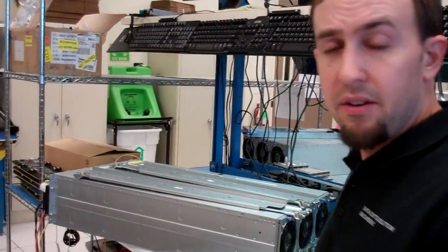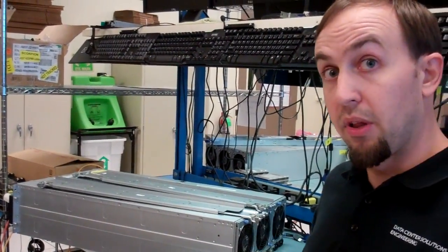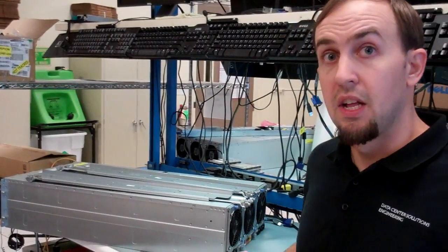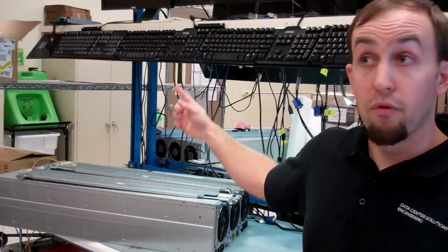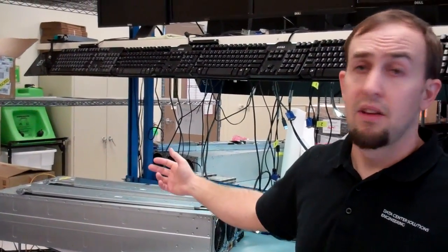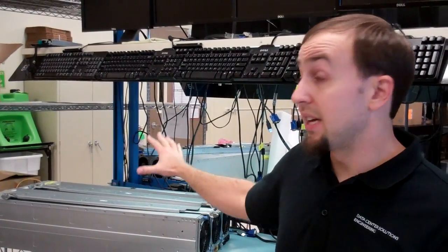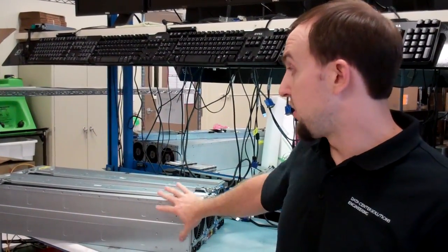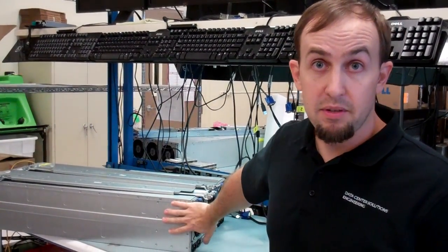For full power redundancy, you want to make sure you plug in both cables on both sides. That will make sure that all four power supplies in the power supply sleds will power up and provide full redundant power for the system.